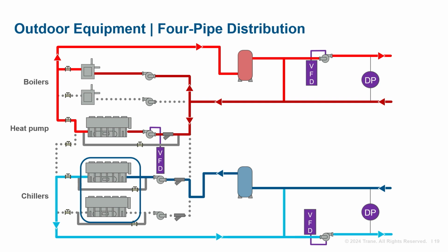Here, there are two. If gas is still not banned, some building owners are choosing to retain their existing boilers, but only using them as a backup option when the heat pump system is unable to meet the heating requirements due to cold weather conditions. In this scenario, when there are moderate loads and outdoor air temperature, the heat pump carries the heating load with boilers for fewer hours of the year.